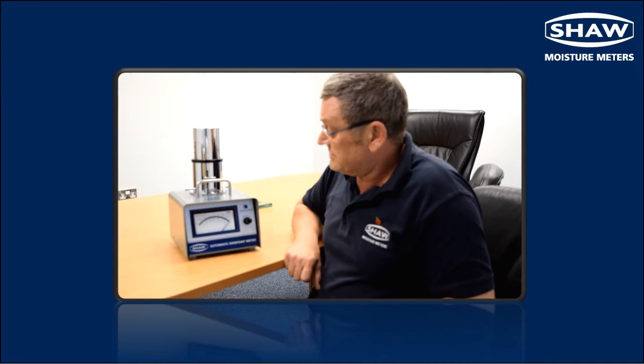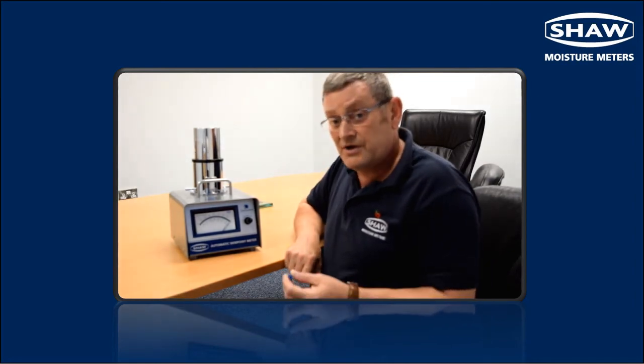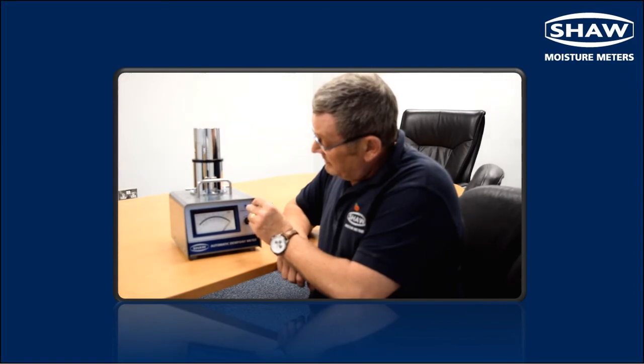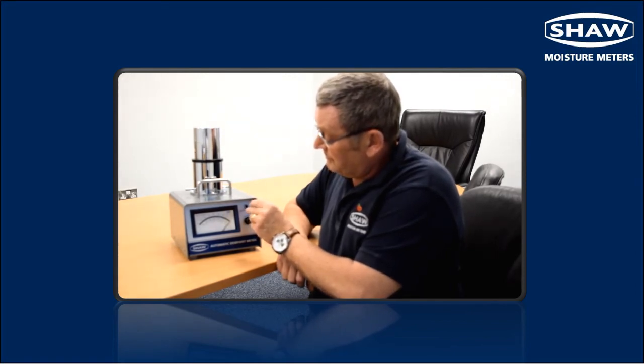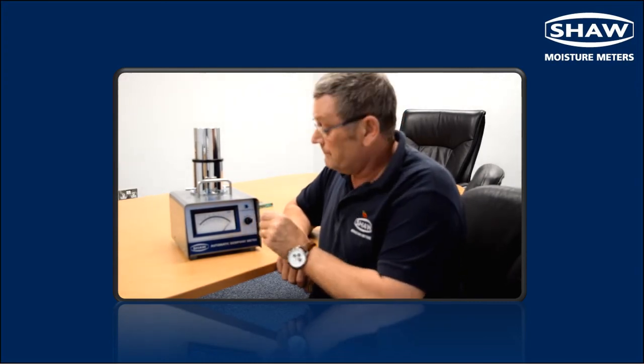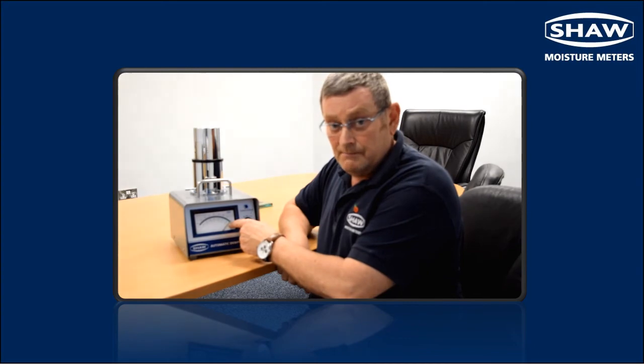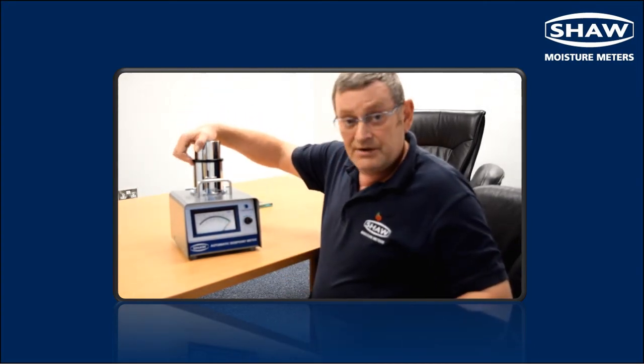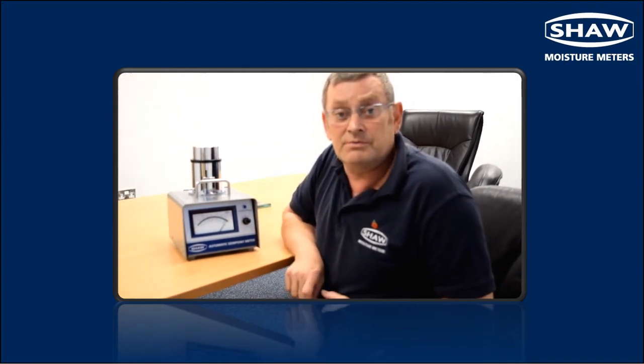Once it has settled, with the screwdriver provided, place it in the automatic calibration pot and adjust the needle to the automatic calibration line on the scale. Close the head of the instrument, and this is all you will need to calibrate the Shaw Portable Moisture Meter.